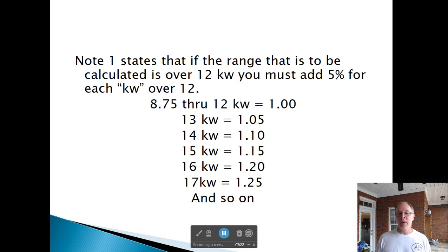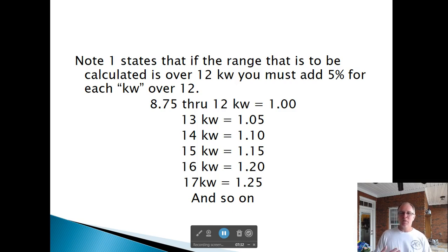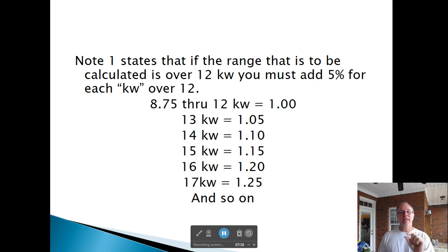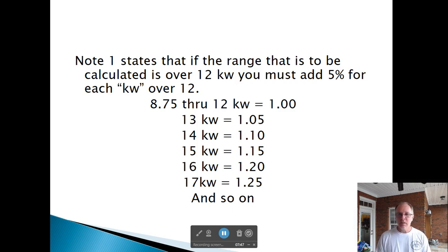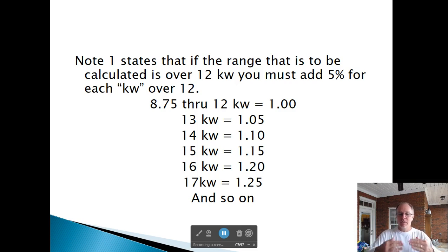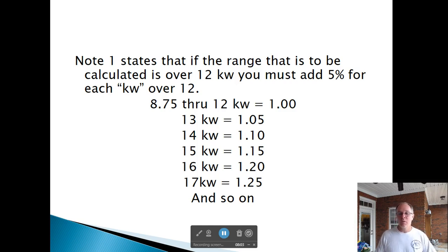So you're adding 5% per kW over 12: 13 kW is 1.05, 14 kW is 1.10, 15 kW is 1.15. A 12 kW range uses a multiplier of 1.00. What is the feeder demand for a 14 kW range? One appliance — Column C says 8 kW — but since it's 14 kW, we add 10%, giving 8,800 watts.